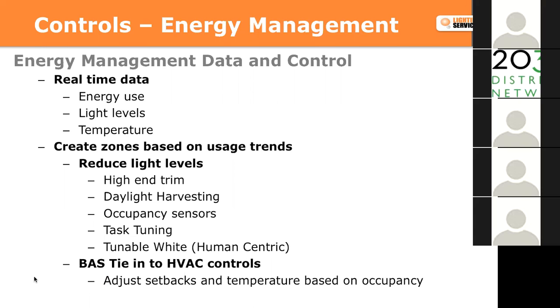Daylight harvesting is another option. These can be a standalone sensor or tied into a fully networked system like this. It can be tricky, those sensors can be a bit fickle, but if implemented correctly they'll automatically dim lights to a predetermined light level based on available daylight. The goal is that occupants don't even know it's happening.